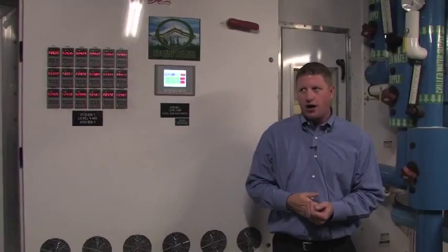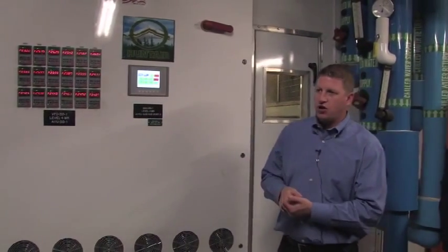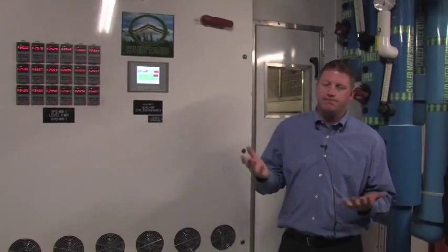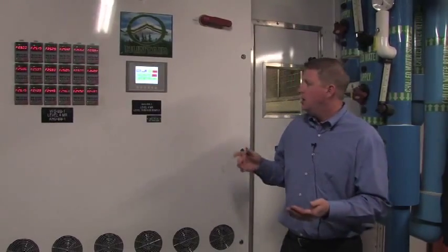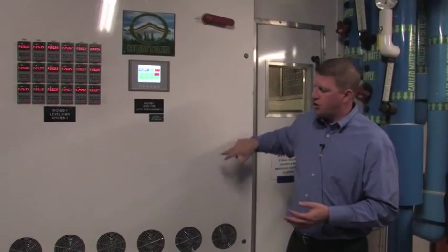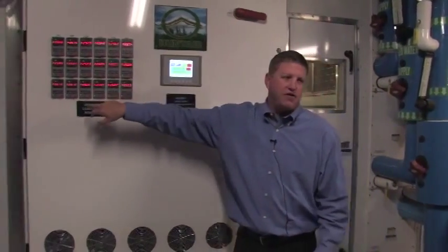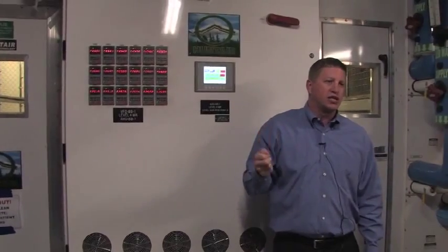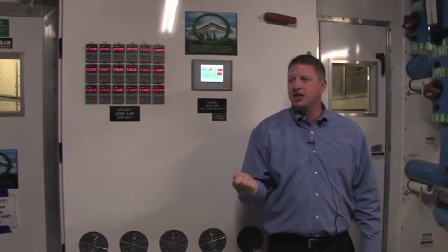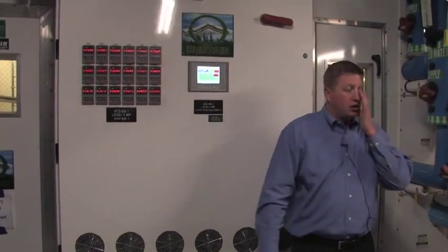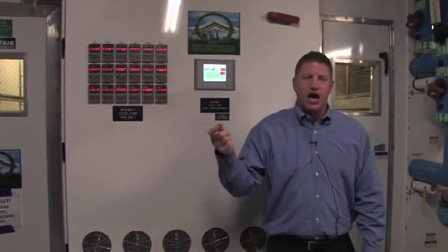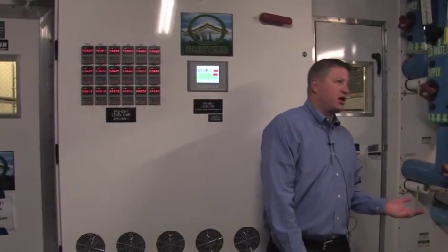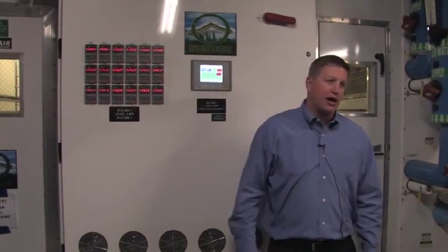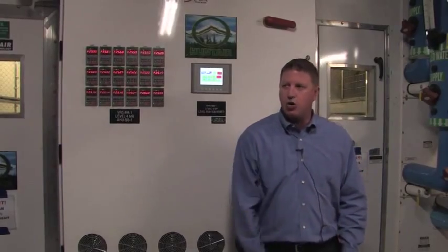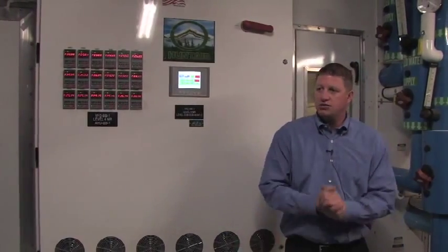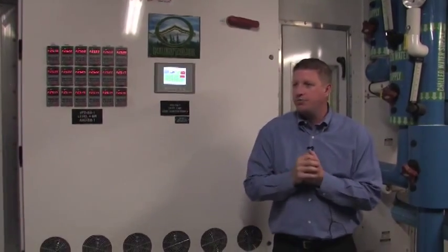From that point, I'd recommend if you're leaving it off for a long period of time, or more than an hour, you come in, you shut the panel down, you go inside, because each motor and VFD combination has its own individual disconnect. So you actually would open the disconnect so it could never come back on. Because Forrest could be walking through and he could diagnose it. Somebody else could come walking through and say, hey, that motor's off, I'll turn it back on. But if you've broken the disconnect, it can't come on. Any other scenarios you've seen or want to play through? I know we've been through that one.